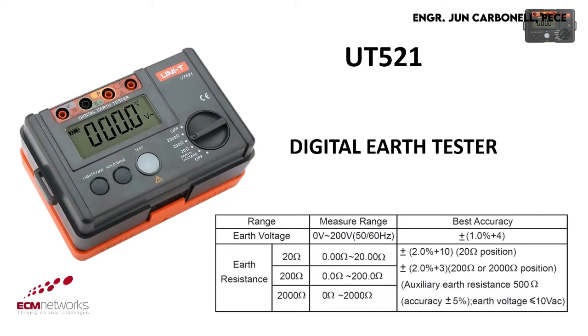Ideal value of earth resistance depends on the utility. But here in the Philippines, for the telco utility, the ideal value is 5 ohms and below. During the test, higher range should be selected, meaning start with 2000 ohm range, then 200 ohm range, and if still lower than 20 ohms, use the 20 ohm range.